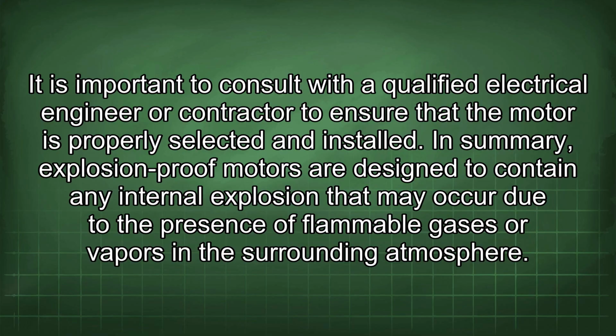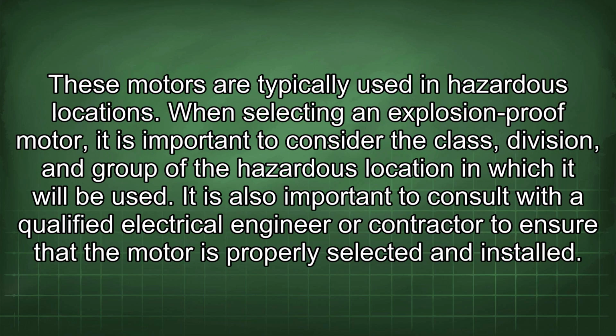In summary, explosion-proof motors are designed to contain any internal explosion that may occur due to the presence of flammable gases or vapors in the surrounding atmosphere. These motors are typically used in hazardous locations. When selecting an explosion-proof motor, it is important to consider the class, division, and group of the hazardous location in which it will be used. It is also important to consult with a qualified electrical engineer or contractor to ensure that the motor is properly selected and installed.